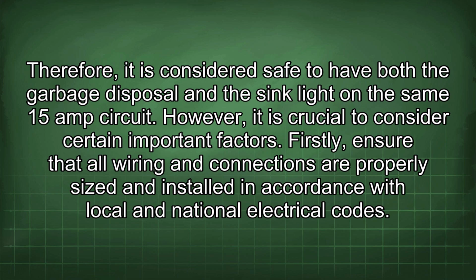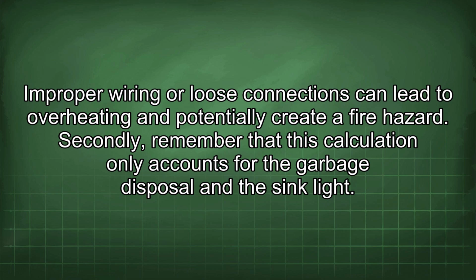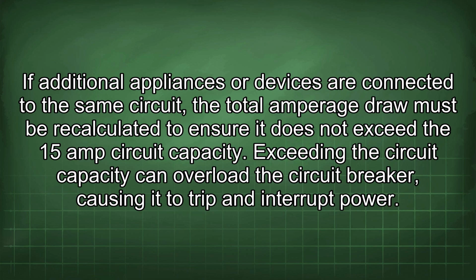Firstly, ensure that all wiring and connections are properly sized and installed in accordance with local and national electrical code. Improper wiring or loose connections can lead to overheating and potentially create a fire hazard. Secondly, remember that this calculation only accounts for the garbage disposal and the sink light. If additional appliances or devices are connected to the same circuit, the total amperage draw must be recalculated to ensure it does not exceed the 15 amp circuit capacity.